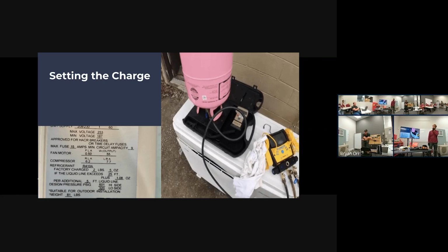When it says high side and low side pressure, keep in mind this is a heat pump, which means that everything that's outside that condenser is actually always going to be on the high side in heat mode. So when you're pressurizing outside the equipment, that's why you can pressurize over 320. In fact, most manufacturers recommend it. You would not go over 600 psi. But again, remember the weak point on almost every system in terms of pressurization is actually the fusite plug on the compressor. The compressor shell is actually low pressure, and that's what you don't want to pressurize to that higher pressure. So if you're pressurizing inside the condenser on the low side of the reversing valve, i.e. the compressor shell, you wouldn't want to pressurize that over 320 psi.